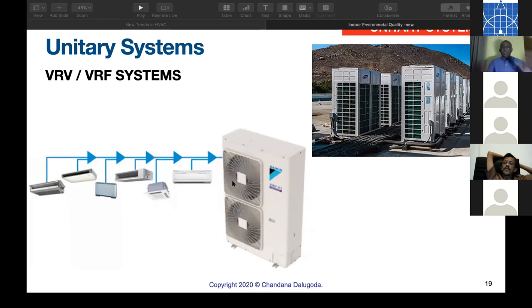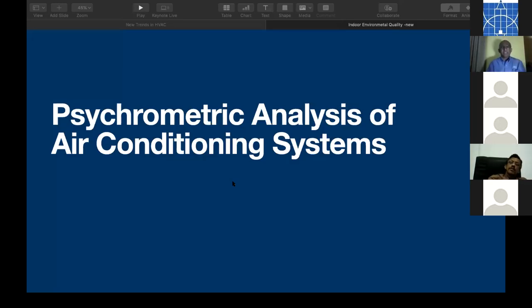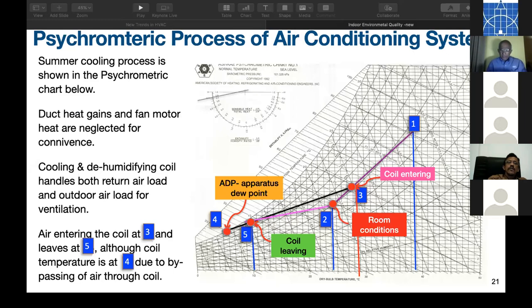So that is some glimpse of basic air conditioning systems. I would like to go through psychrometric analysis also, because only then can we really see these new systems and their constraints. Let me discuss very quickly the psychrometric process for comfort cooling. Outdoor air is introduced to the air conditioning apparatus. The room air and outdoor air mix together and enter the cooling and dehumidification coil. What happens is a cooling and dehumidification process. At the end, air leaves the cooling coil at a lower temperature.